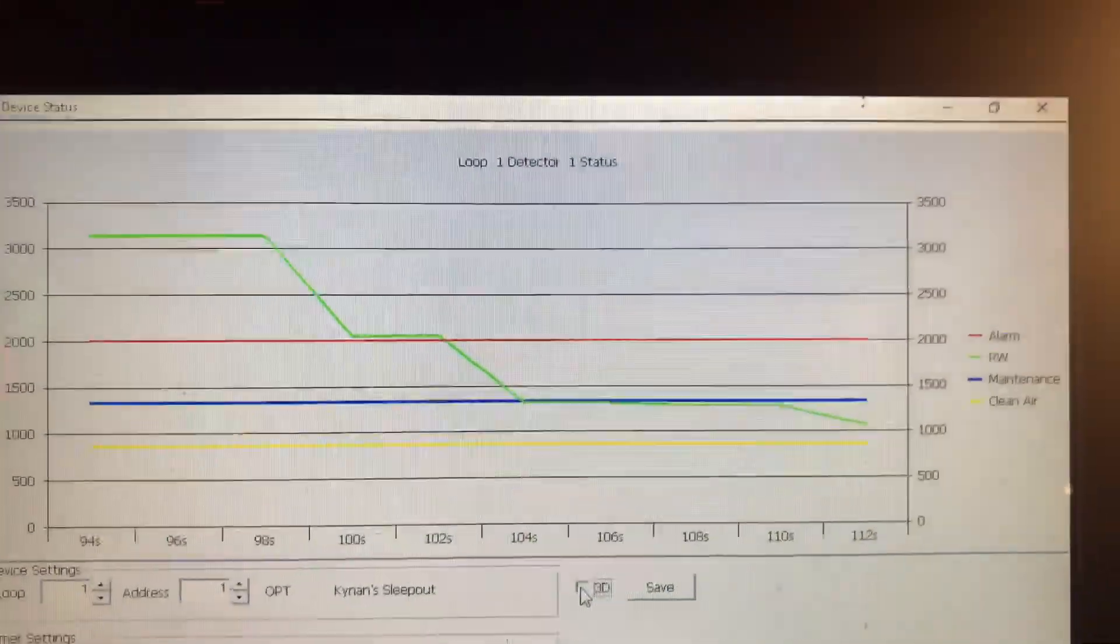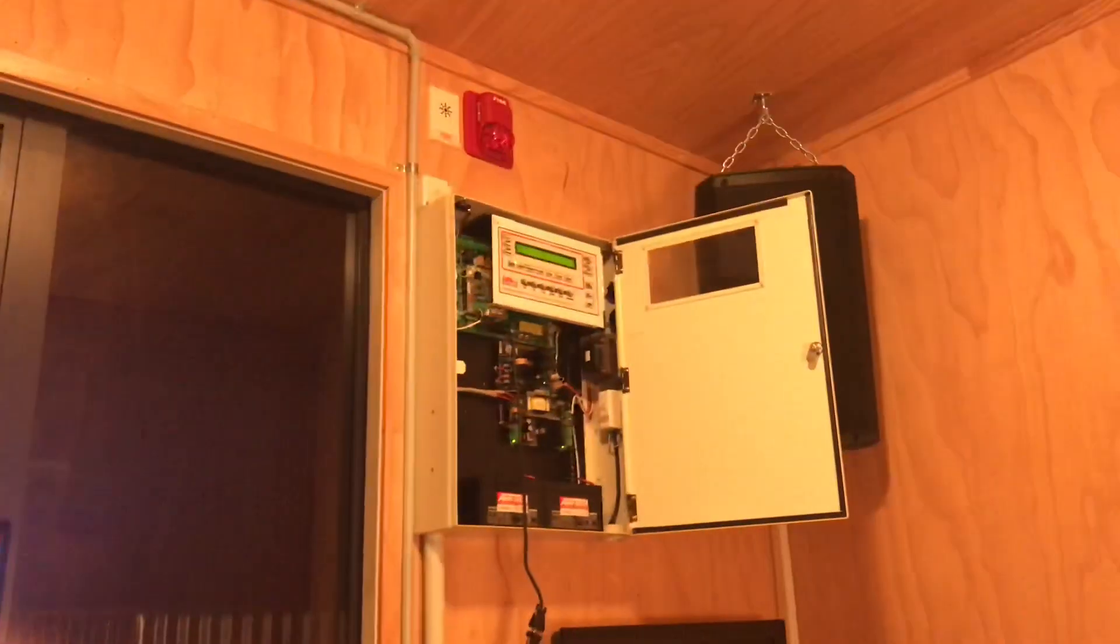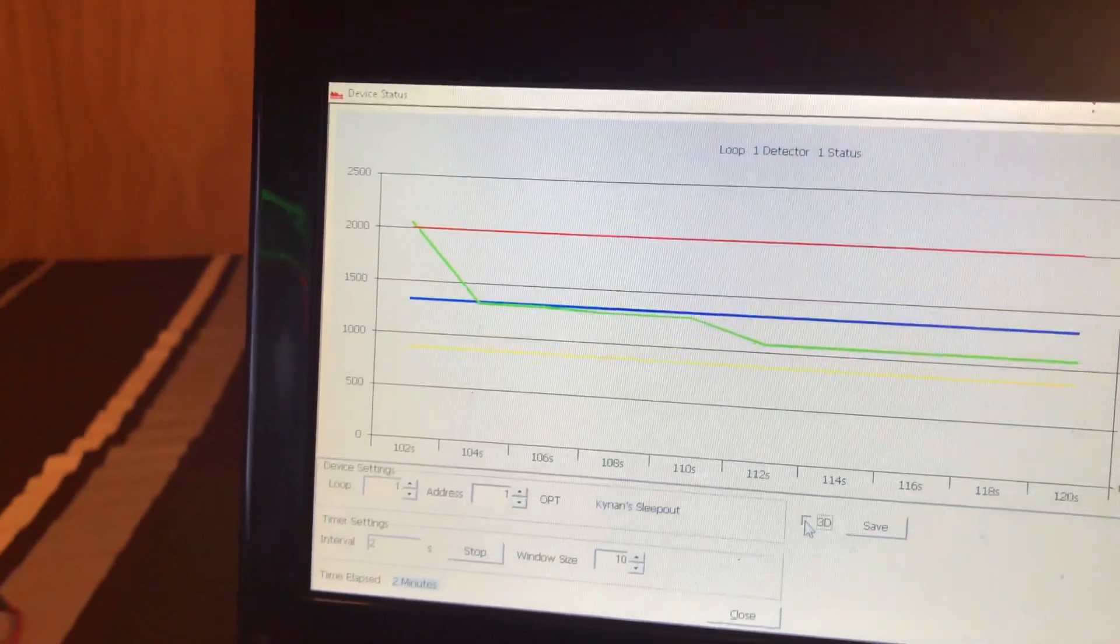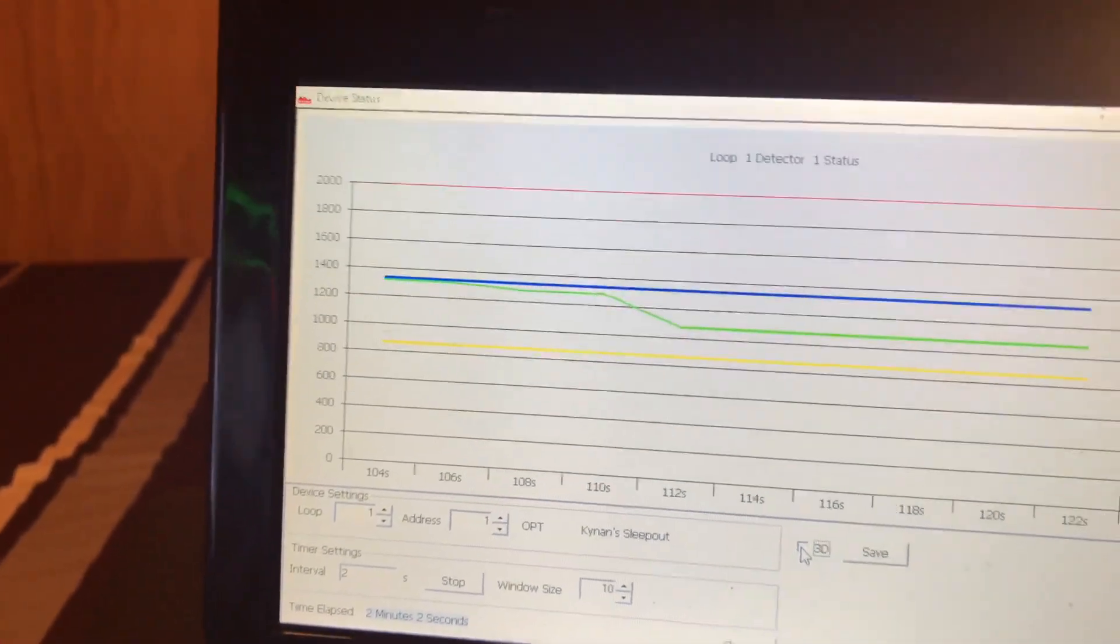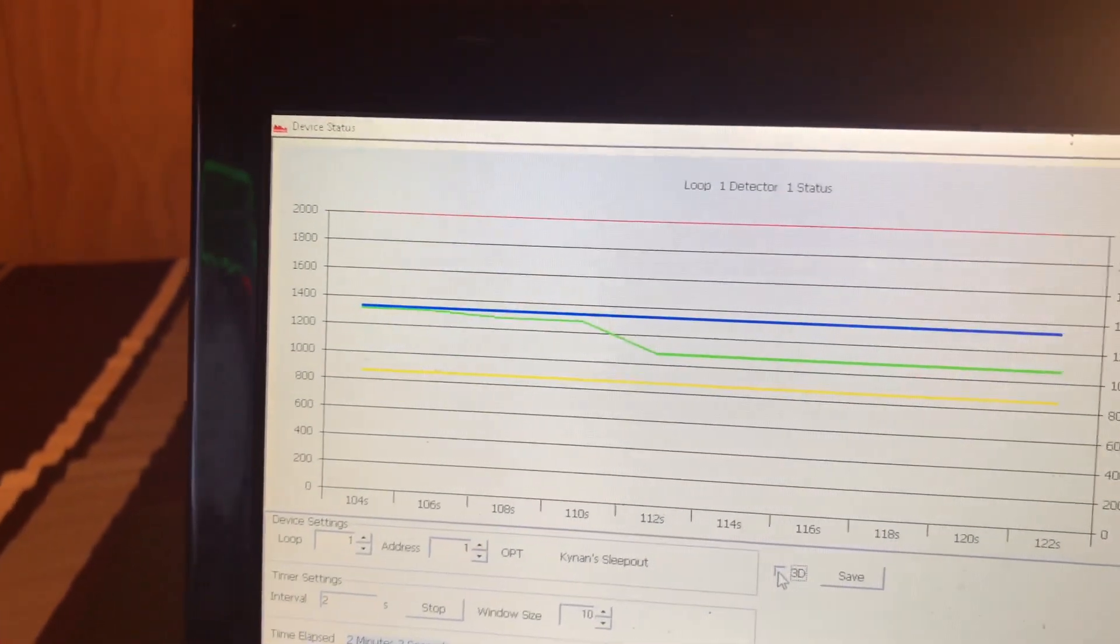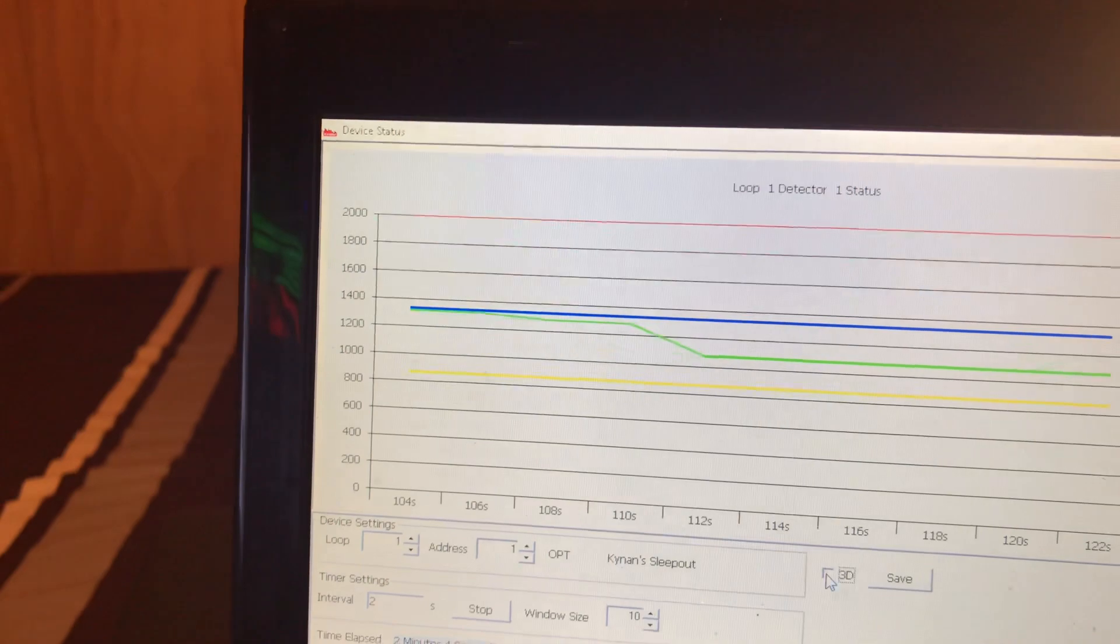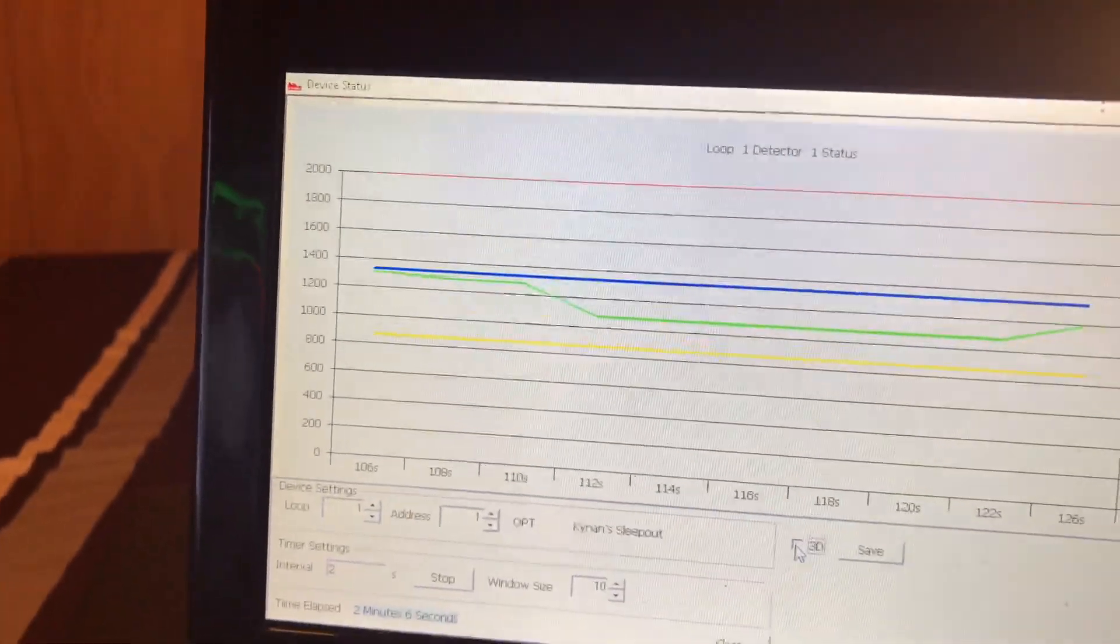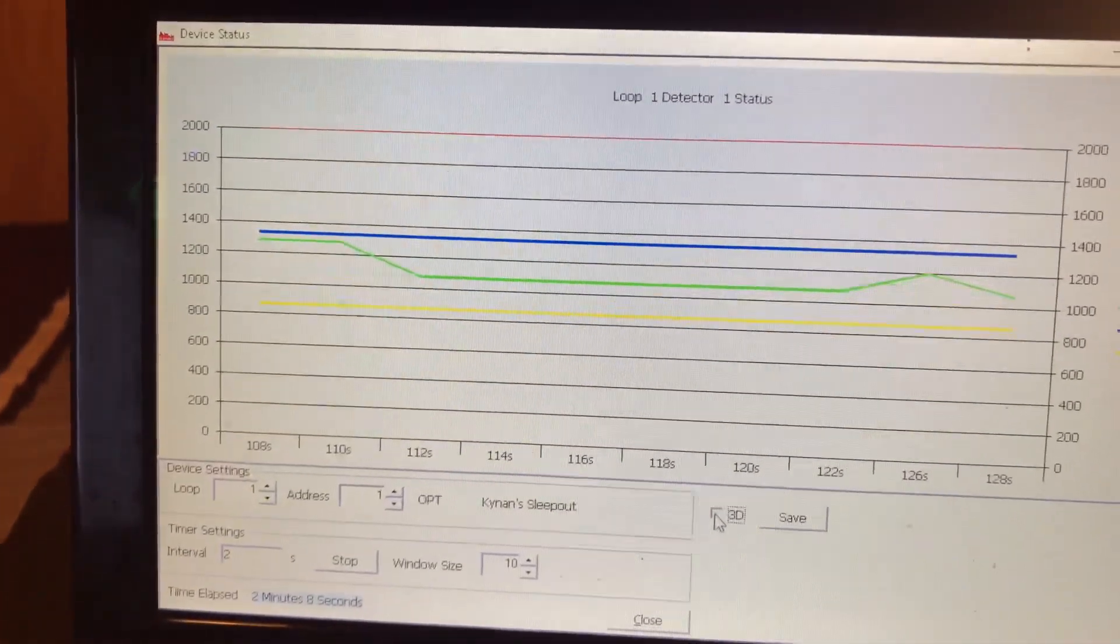So that wasn't enough to set it off. As far as the panel is concerned, the system is still normal. But that gives you a good idea of just how sensitive the smoke alarms really are. But there is something in the smoke alarms called gating, which avoids false alarms and that's why the value rose so much.